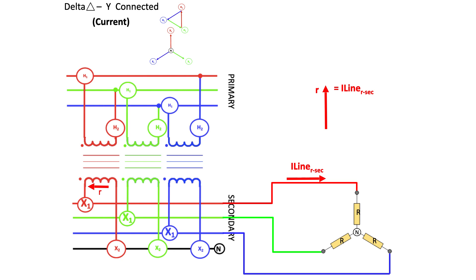The power is going to be coming from the primary side connection because the load is on the secondary. So the currents on the red phase as well as the other phases are going to be flowing into the dot of the primary winding. And if the current is flowing into the dot of the primary, it has to be flowing out of the dot on the secondary. A similar relationship holds true for the other two phases.